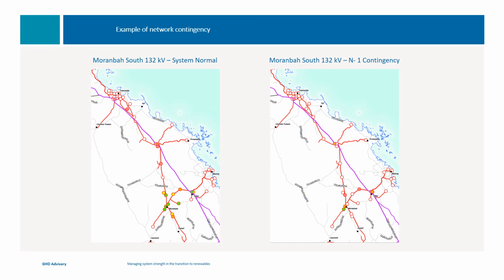The diagrams here show the impact of putting a single 400 MVA synchronous condenser at Moranbah South. The green dots show very high system strength provision flowing through the yellow, orange and then red, and then white is no benefit. And as you can see, on the 400 kV network and some of the subtransmission network, there's good system strength provision.